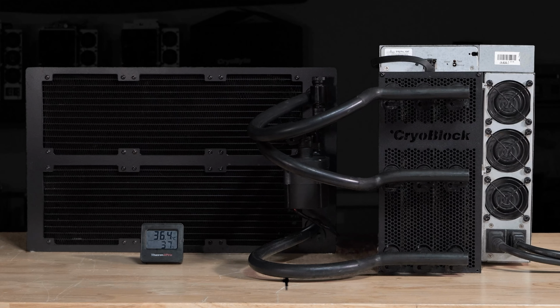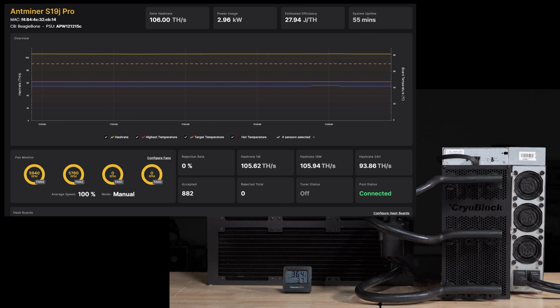Test 2 is maximum cooling. In this test, we again jump in at the 55-minute mark, and we'll fast forward to the end of the test, highlighting the consistency in temperatures. We have our back fans running at 100%, and our radiator fans running at close to 100% as well.